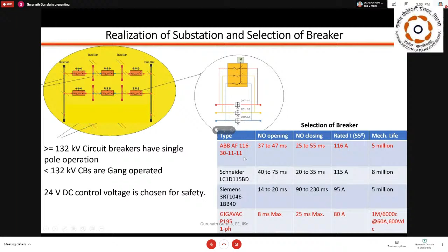So in order to enable that kind of operation, we have used three single phase contactors as well as one three phase contactor, so that you can achieve both operations in the system. The single phase contactor has a very small operating time, so that you can mimic a circuit breaker operation reliably. It's not exactly reproducing any of the transient behavior of circuit breakers, but for power systems analysis, it is enough if the circuit breaker can act as a switch. So I think this is more than enough for our kind of applications.